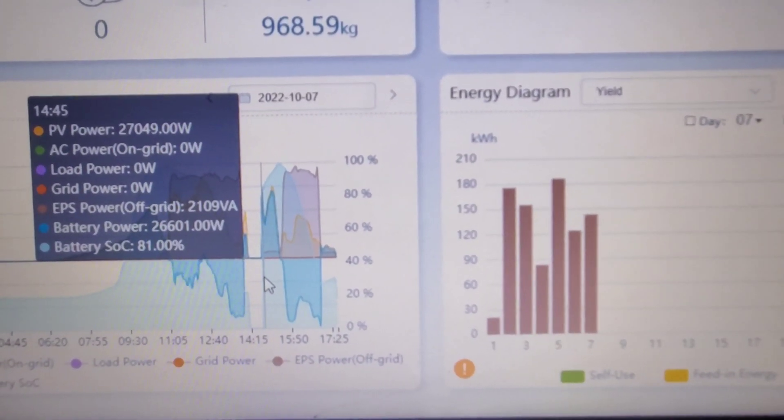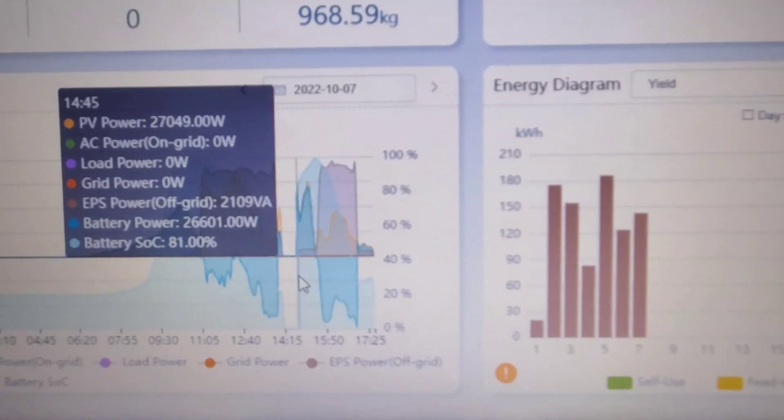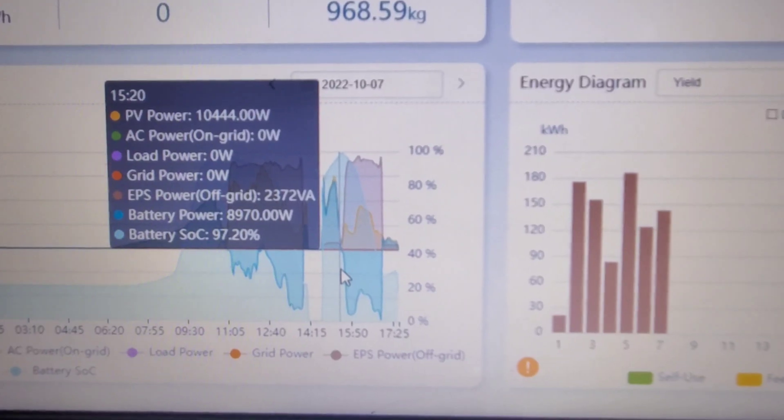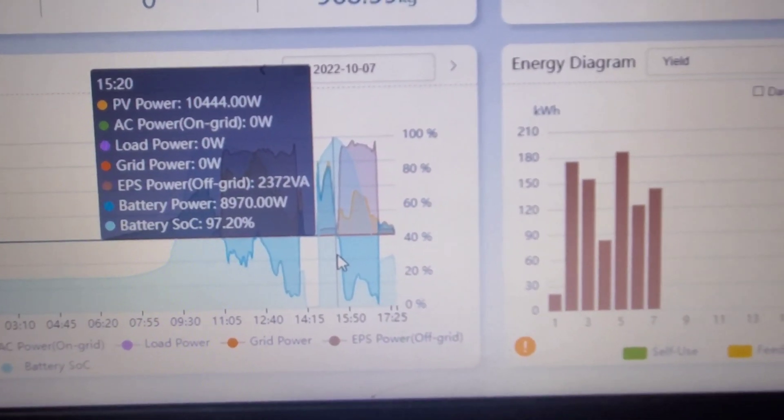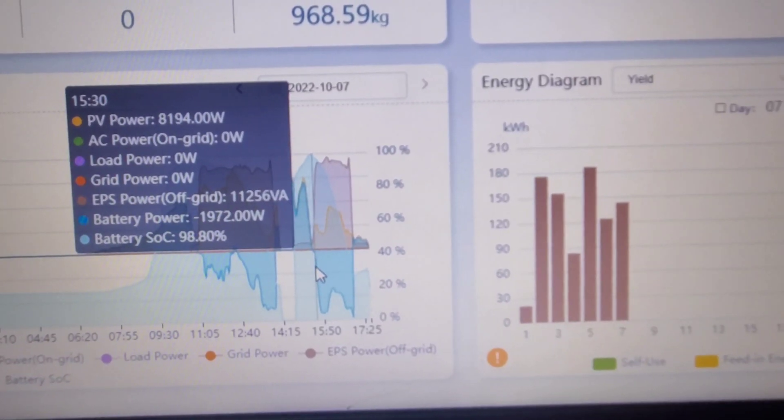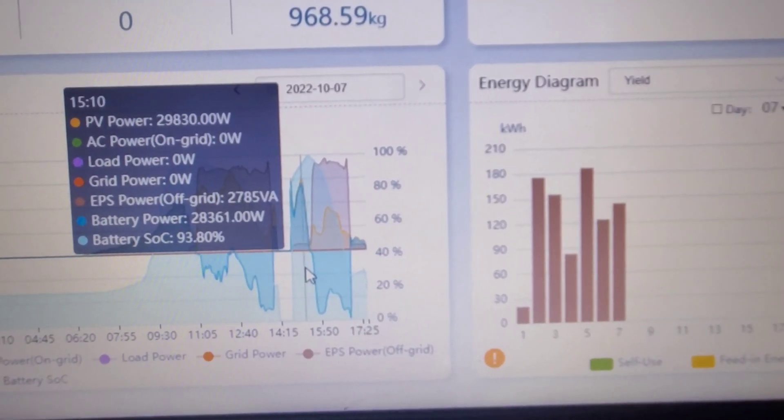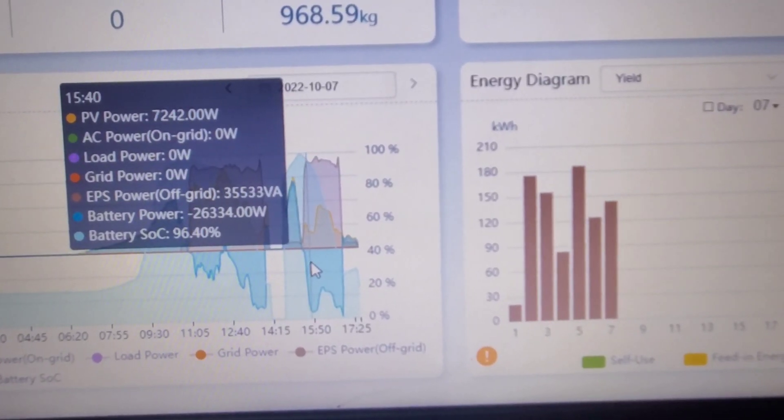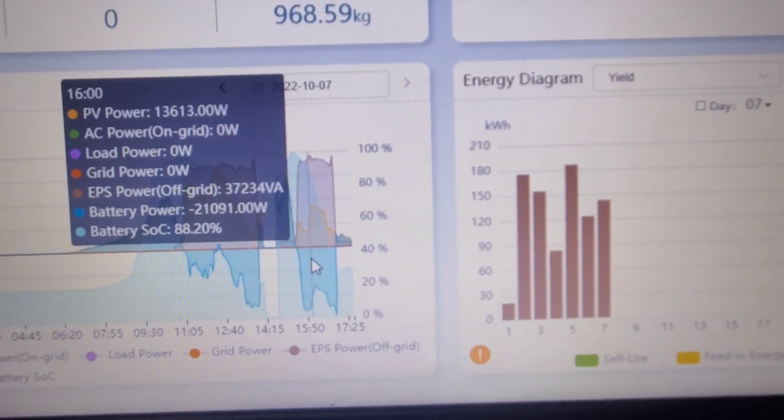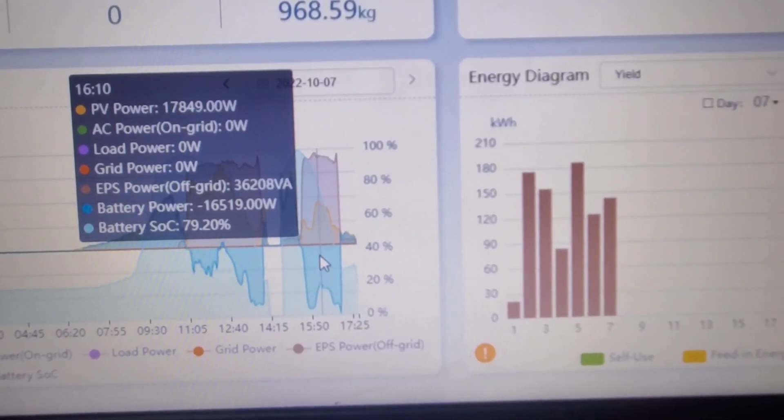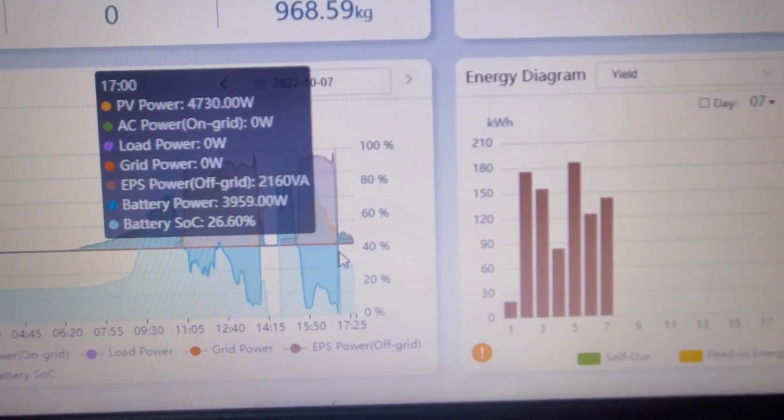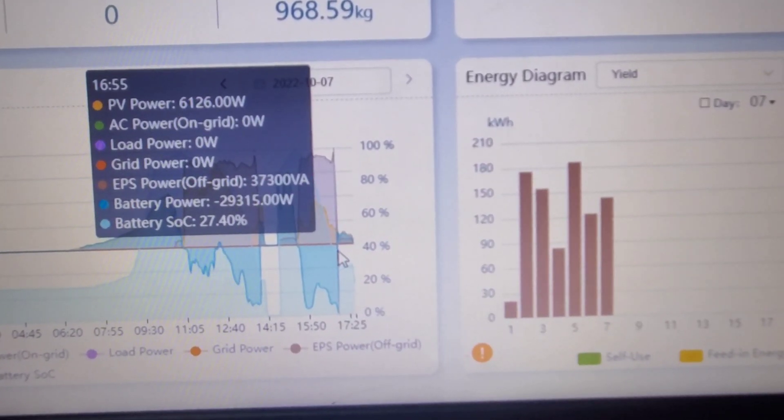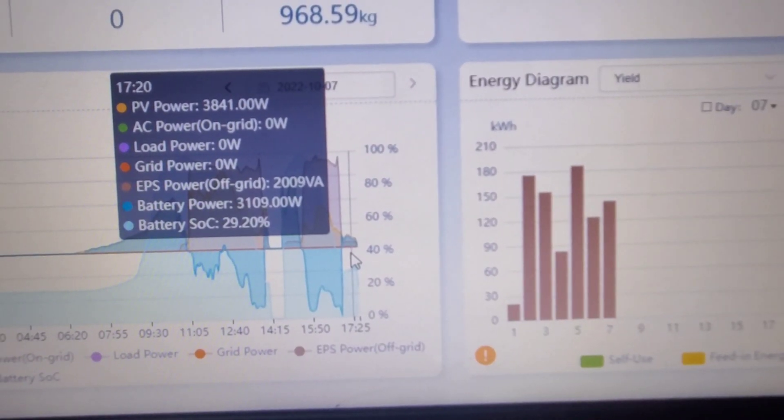It's the last set of batteries that are giving us the hardest time. We're at 14:45. We're charging the batteries now at 28 kilowatts—that's all five inverters combined. Then we put the load back on. It starts at 16 kilowatts and slowly rises till we get to 39 kilowatts.